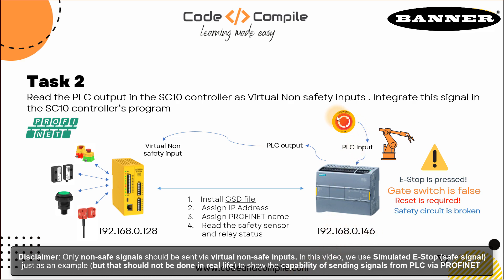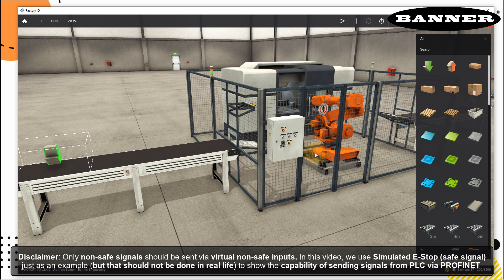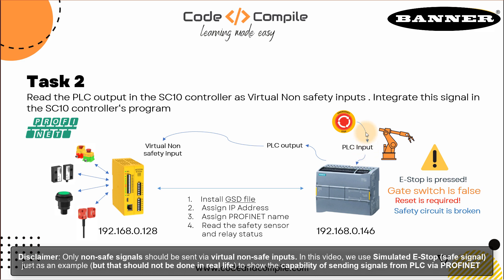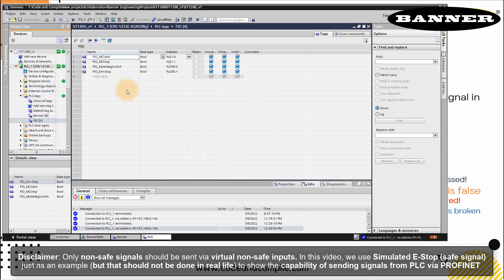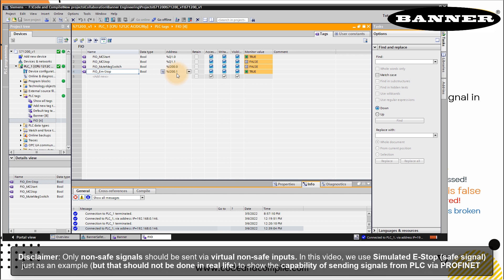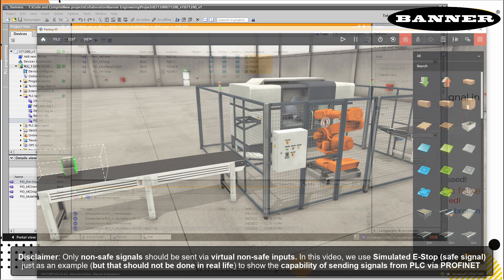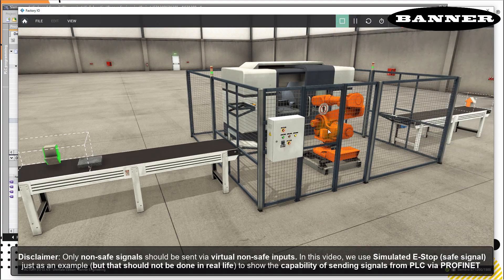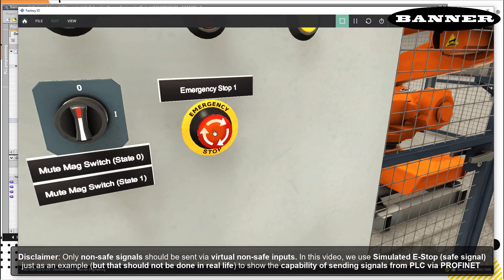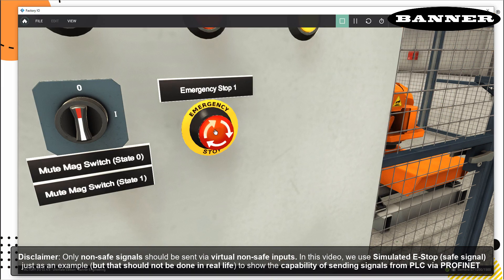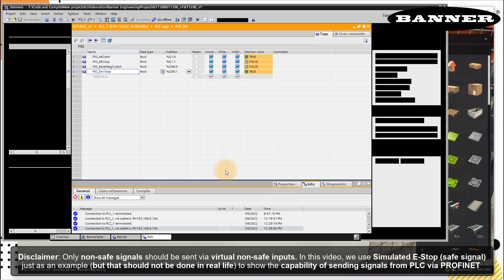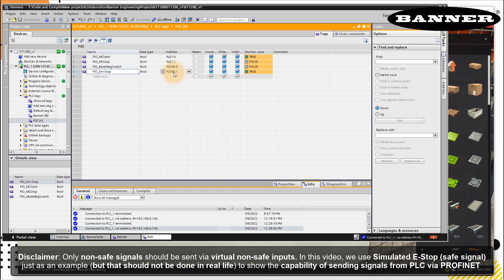In the PLC, I am connecting this PLC to the Factory IO just for the demonstration — maybe you have a real-time application. Let's imagine your PLC input is connected to an e-stop button. In our case, if I show you my tags, my e-stop button is connected to the input i200.1. At the moment you can see it's true because e-stop is always NC. If I go play and press it, it's now false. So by default it's NC. We have seen the status that my e-stop is connected to one of my inputs, i200.0.